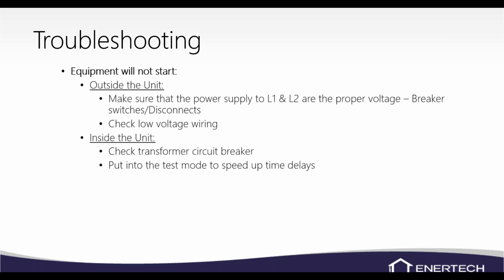You can go ahead and put the unit in test mode. It'll speed up your time delays. Now, when it's in test mode and it speeds up, if let's say you have a high pressure lockout, our high pressure lockouts now, if it sees an open switch, the unit will not even try to start the compressor. And when you're in test mode, it'll do it so fast that it won't even give you what we call a soft lockout. It'll immediately give you a hard lockout. And so you won't even try to start. In test mode, those time delays in between restarts are shortened. So all of a sudden it'll go into a hard lockout and not try to start. So when you do have it in test mode, it'll just speed up your time delays is what that does. And the status light will go out on that lockout board.